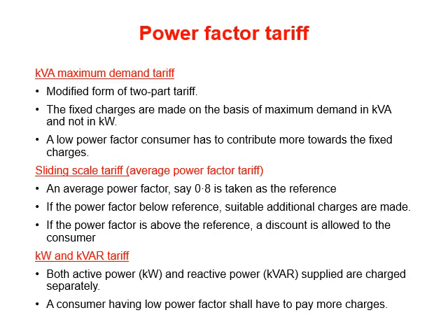So what is kVA maximum demand tariff? It is a modified form of the two-part tariff we saw earlier. The fixed charges are made on the basis of maximum demand in kVA and not in kilowatt. A low power factor consumer has to contribute more towards the fixed charges. Who uses the low power factor, they have to pay more.